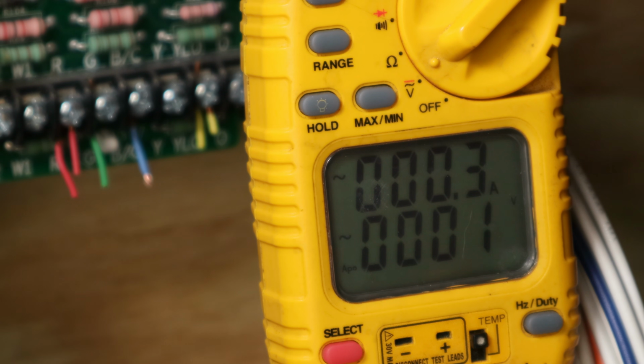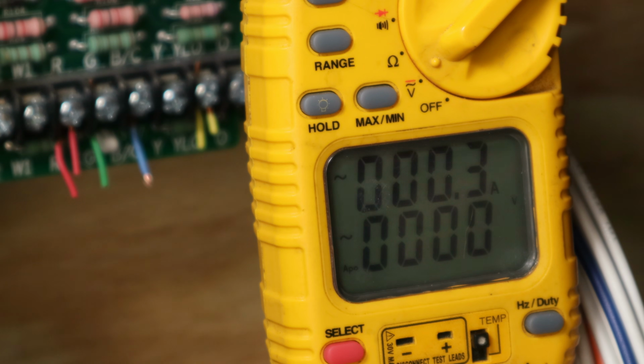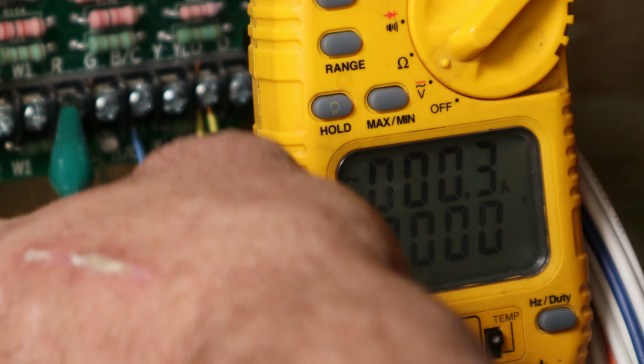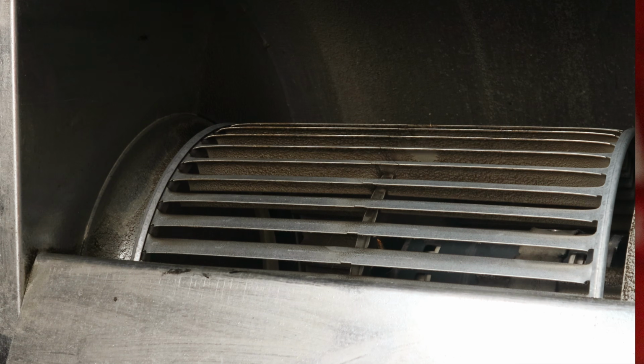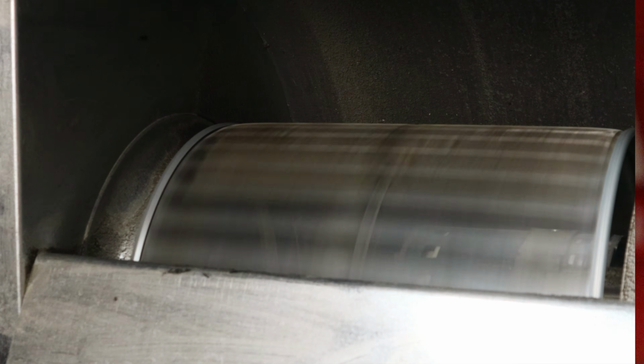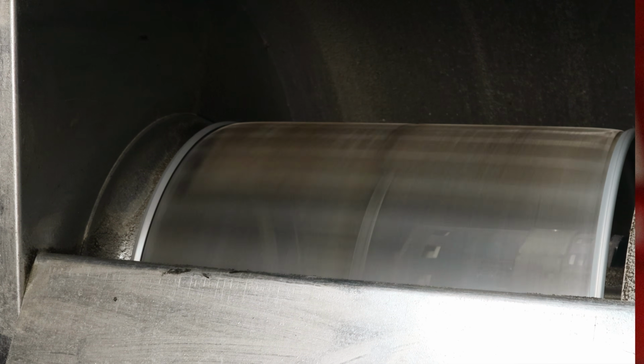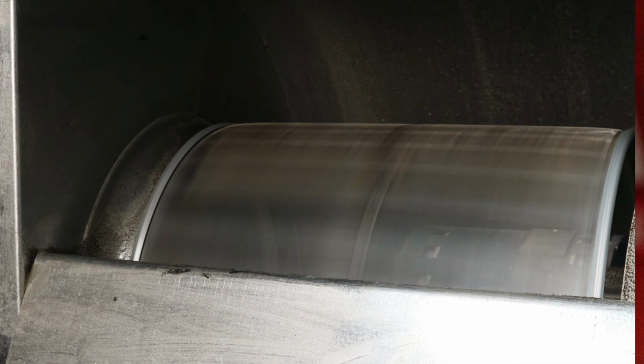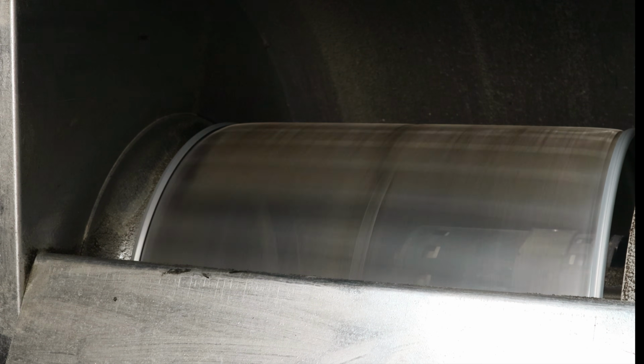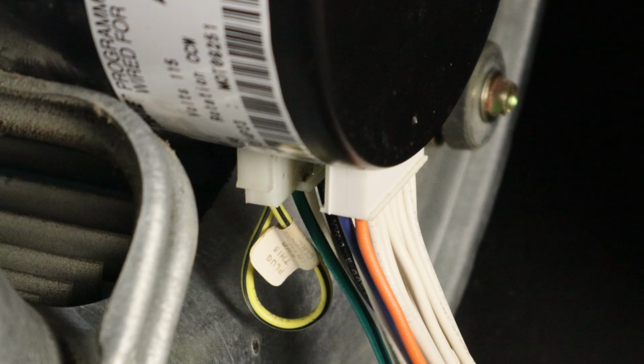And as long as I have a signal for the blower to turn on, that signal should be sent through those communication wires to turn on the motor. So what I'll do next is I'll just take a jumper and I'll go between R and G just to give it that signal. The purpose behind what I'm doing here is I'm making sure the thermostat or any wiring to or from the thermostat is not the problem. By jumpering it out, I can eliminate that as a possibility. So in this case, if the blower starts like you see here, I might start looking at the thermostat and the wiring. Now let's say the motor didn't start.